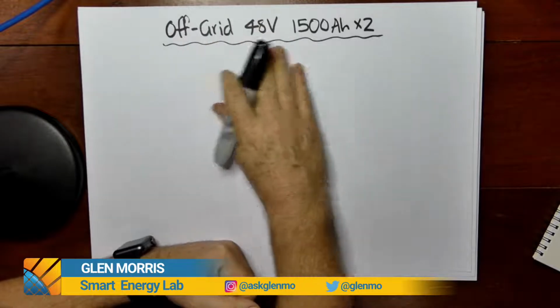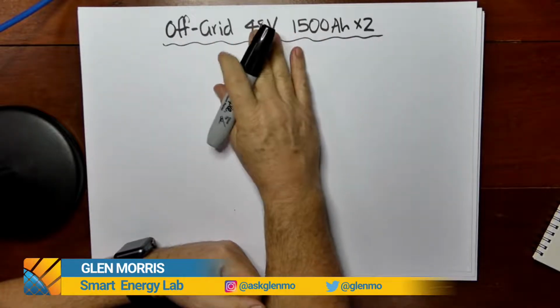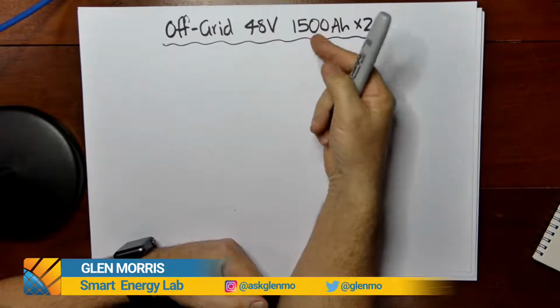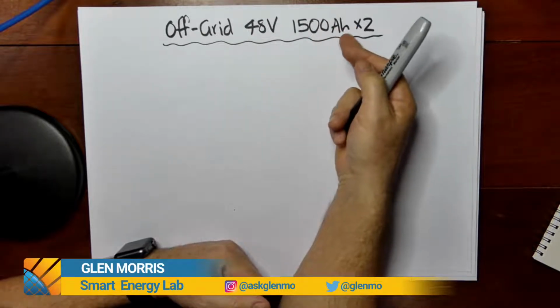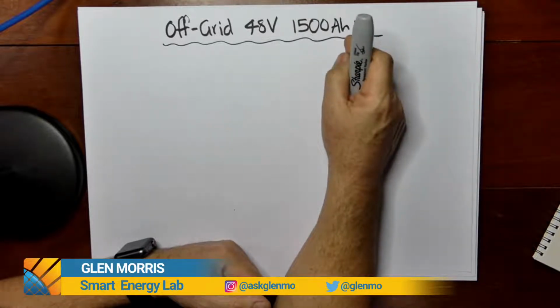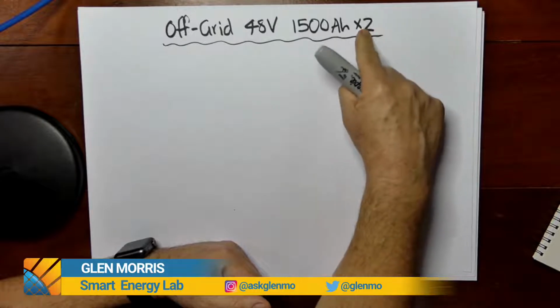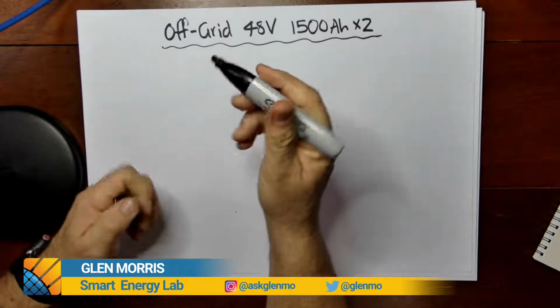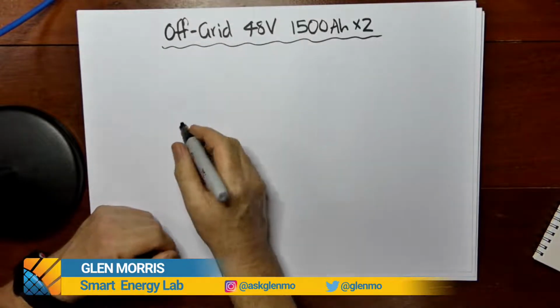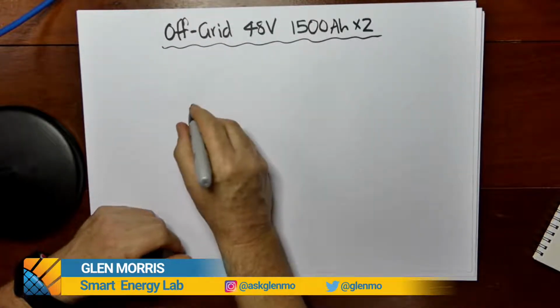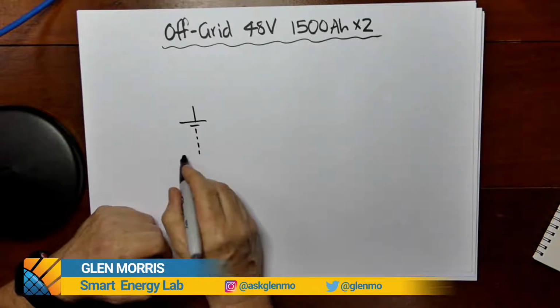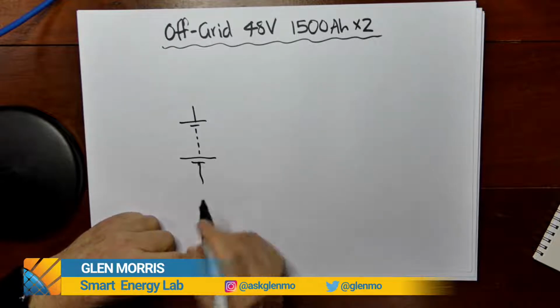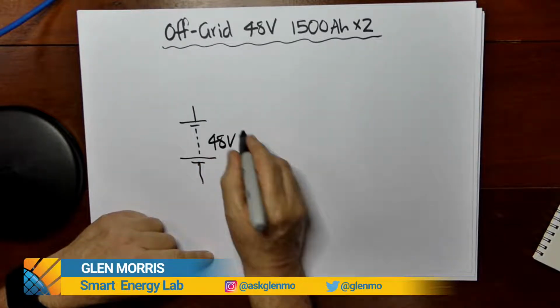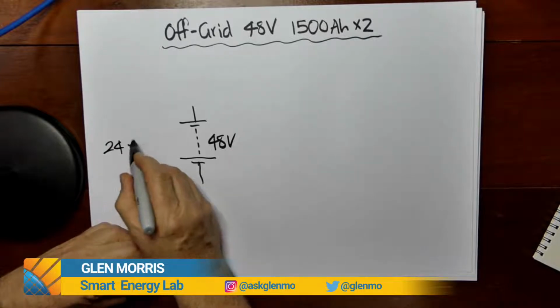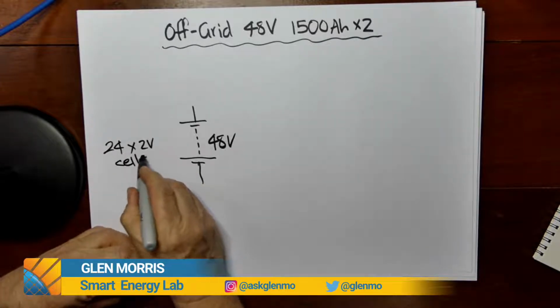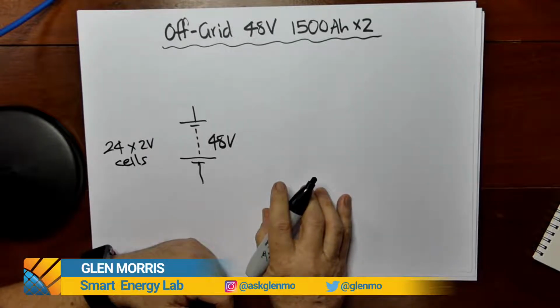I'm going to design a fairly chunky off-grid system. It's a 48 volt battery. We've got 2 strings of 1500 amp hour sealed lead acid batteries. That's a fair whack of energy stored in 2 strings, so times 2. I'm going to draw it in simple electrical symbols. This is a symbol for a cell, and we've got multiple cells, and there we go. That is 1 string of 48 volts, made up of 24 2-volt cells. That's a traditional 48 volt system.